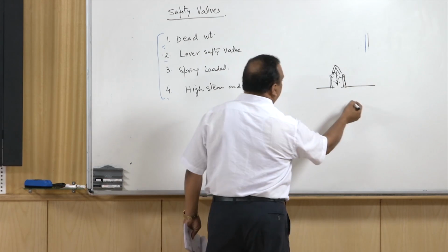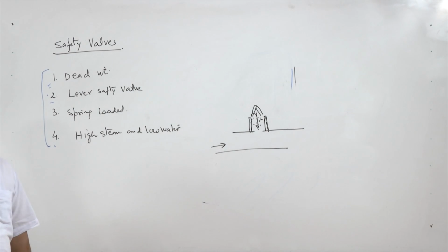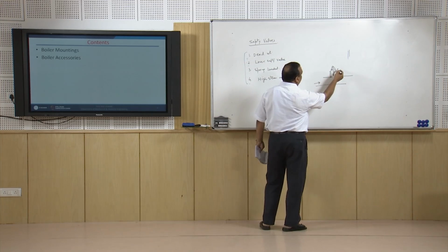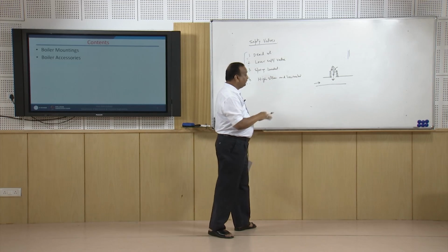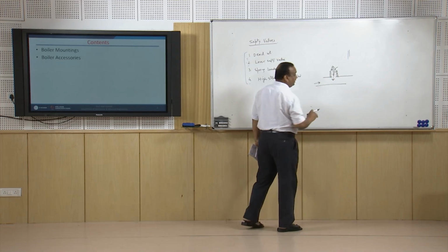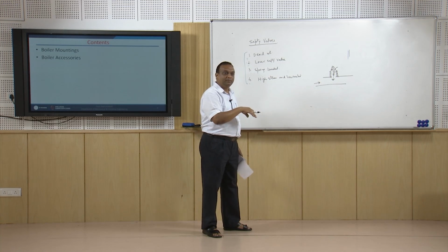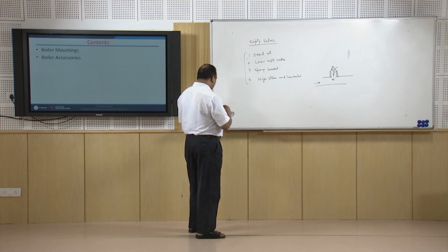and ultimately the heating in the boiler will slow down, or it will be reduced, right, and in that case the accident can be prevented. But when this becomes operative, we will have to replace this fusible plug with another fusible plug, and then the boiler can be restarted. Now after the fusible plug, there is the steam stop valve.